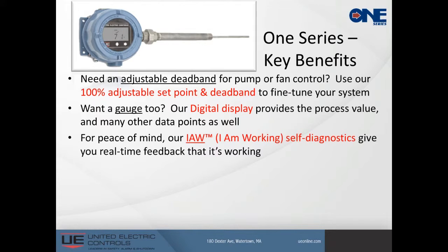Now, for peace of mind, of course, this device is self-diagnostic. It has a patented capability that tells you quite a bit. It gives you some key interfaces between its health, so you can monitor the process sensor to determine if that sensor becomes plugged or not. You can also monitor all of the electronic functions of the device, and locally it will tell you if the product is working, if it is not working, if it's been overpressured or underpressured. It gives you codes across the front so you can diagnose those circumstances and basically take corrective action as it would be.